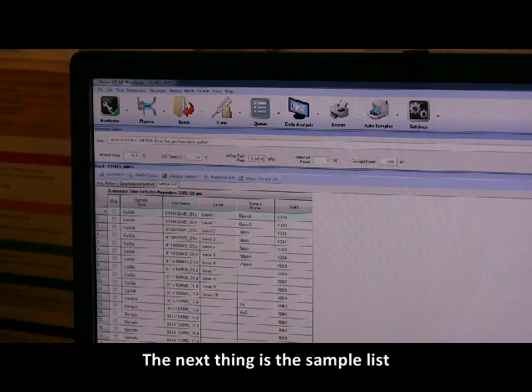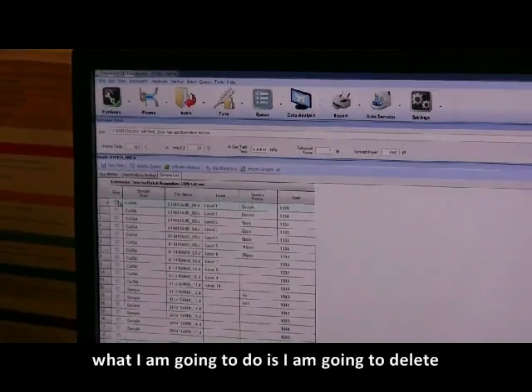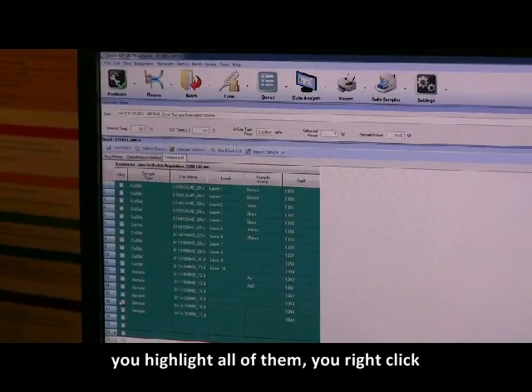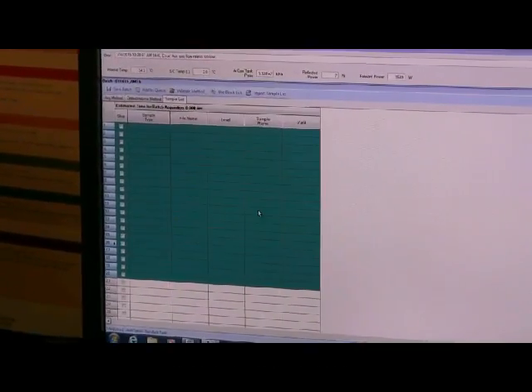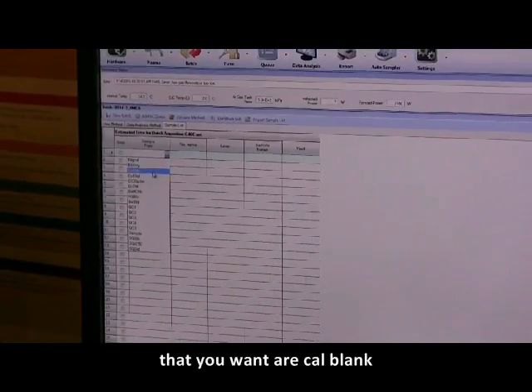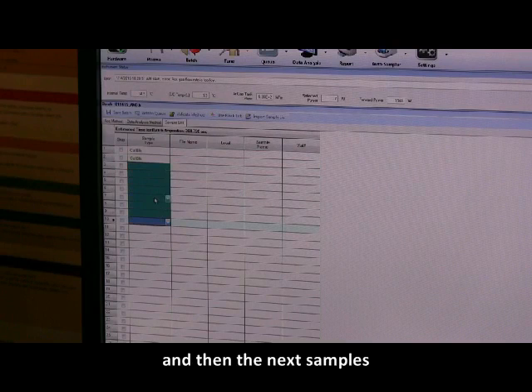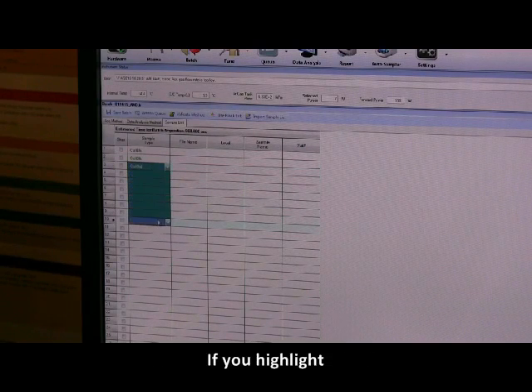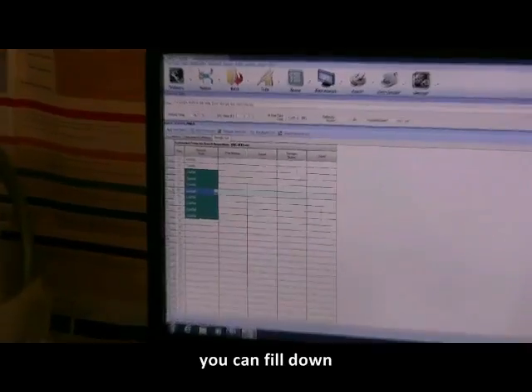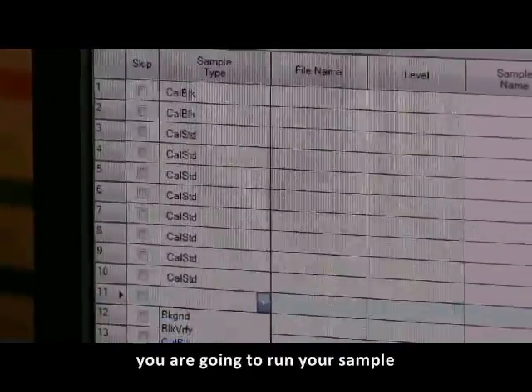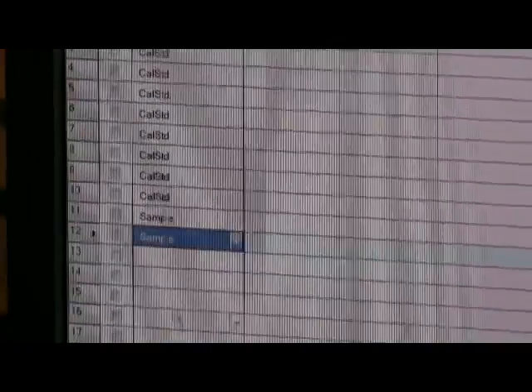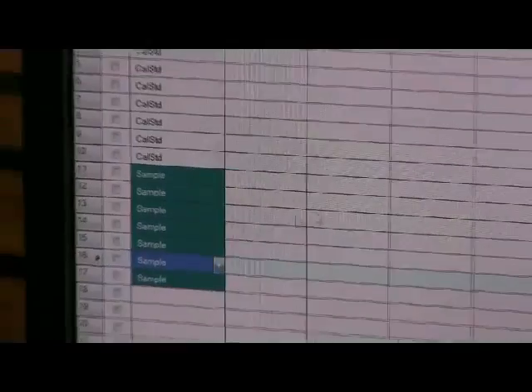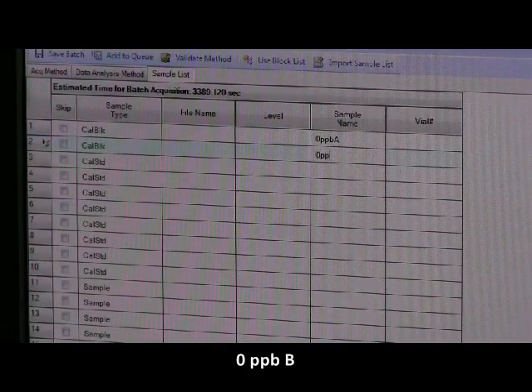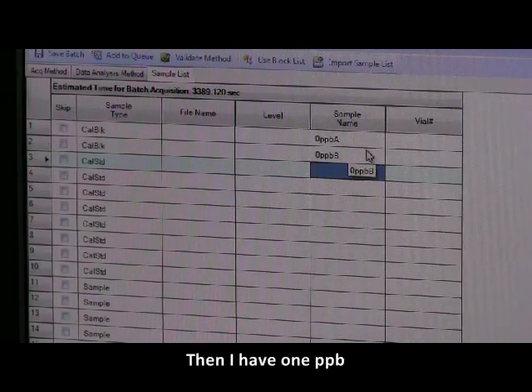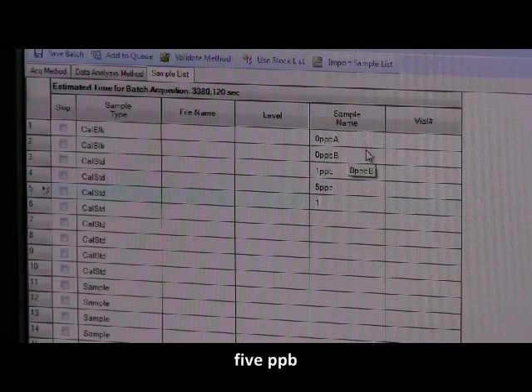The next thing is the sample list. Here I've just given some examples. What I'm going to do is I'm going to delete all of this and just start fresh. You can highlight all of them. If you right click, you can delete all the lines. The first 2 samples that you want are cal blank, and then the next samples are going to be cal standard. If you highlight and scroll down and right click, you can do fill down. After your cal standards, you're going to run your samples. You want to put in your sample name next. So, for example, the first one, 0 ppb A, 0 ppb B, since I have 2 different blanks. Then I have 1 ppb, 5 ppb, 10 ppb, etc.